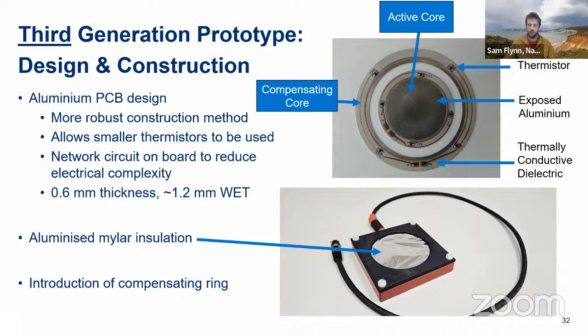That thermistor network I described earlier, we're now embedding on the PCB. That allows us to reduce the electrical complexity and make them a lot more robust. It simplifies the electronics. We're also moving to an aluminized mylar system rather than just cling film. The reason for doing that is aluminized mylar starts to shield some of the infrared, which is known to cause temperature fluctuations. This is demonstrable in a lab environment: if you hover your hand over it, you'll barely see any temperature change, whereas with the non-aluminized mylar, you can see it shoots up. So it's moving in the right direction to being a device that could maybe be used in the clinic.